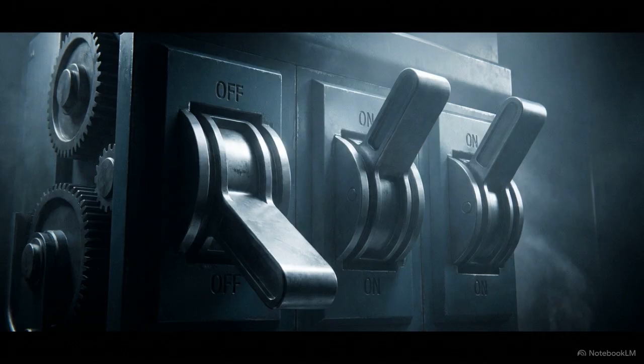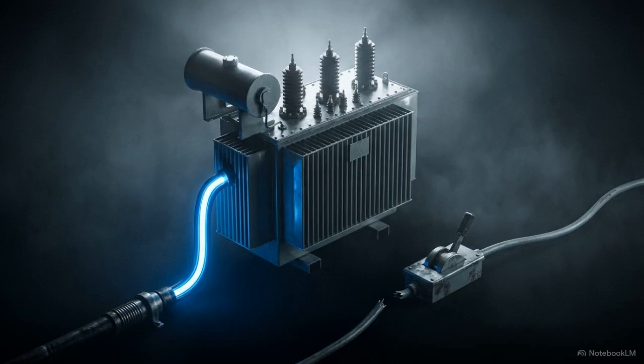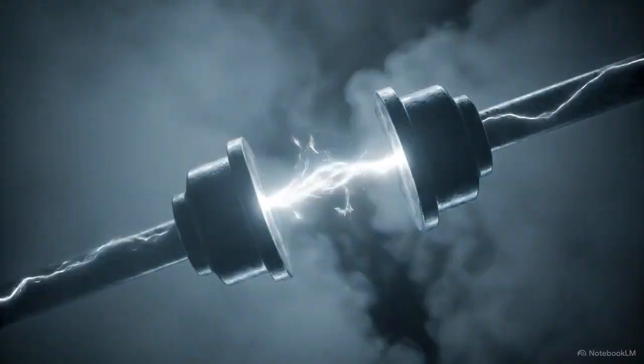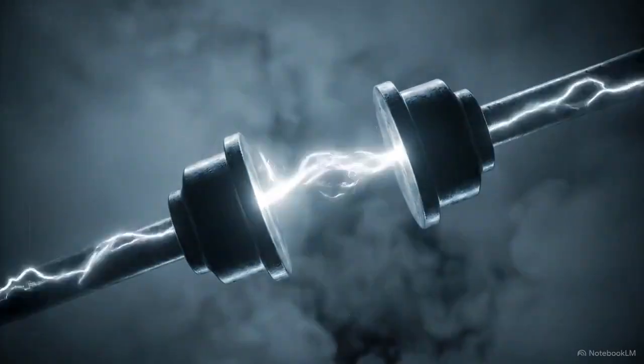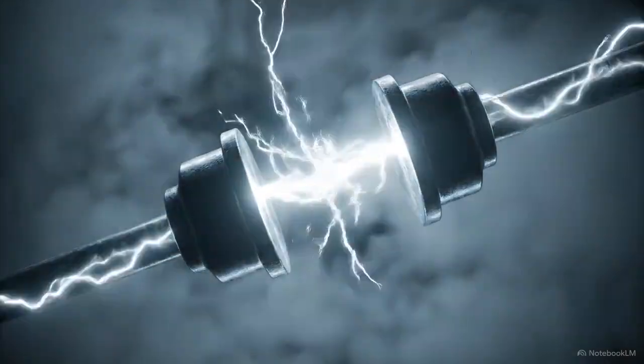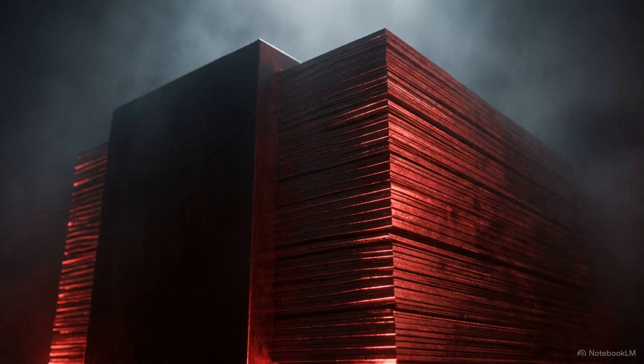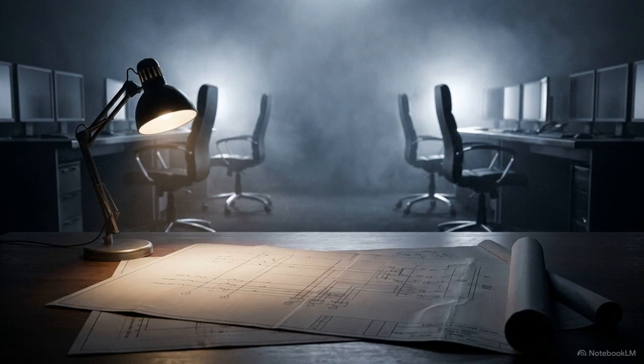The second requirement is a sudden disruption to the circuit, like a single-phase switching event. If a breaker opens on one or two phases, it isolates the unloaded transformer while keeping it electrically tied to that long capacitive cable. That momentary switching action is the final catalyst. It injects an initial transient jolt into the isolated pocket of the grid, providing the push needed to knock the unloaded transformer core right into saturation. For grid planners, this highlights a specific risk. A major instability can emerge solely from the operational alignment of entirely intact hardware.